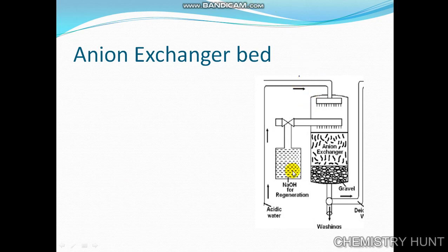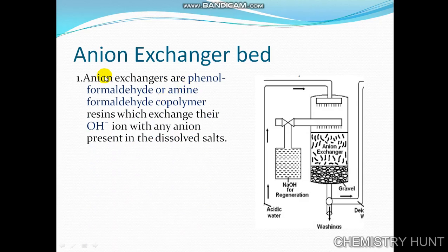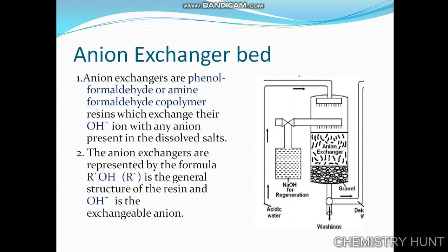Now for the anion exchanger: the acidic water is passed into the anion exchanger where it absorbs all the anions and gives an equivalent amount of hydroxide ions. Anion exchangers are phenol-formaldehyde or amine-formaldehyde copolymer resins which exchange hydroxide ions with any anions present in the dissolved salt. The anion exchangers are represented by the formula R'OH, where R' is the general structure of the resin and hydroxide is the exchangeable anion. All anions are retained in the anion exchanger bed and we get equivalent hydroxide ions.